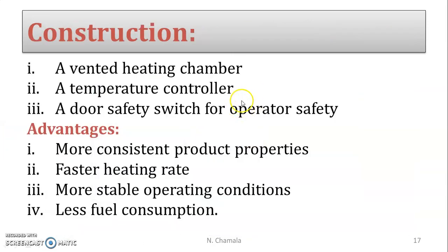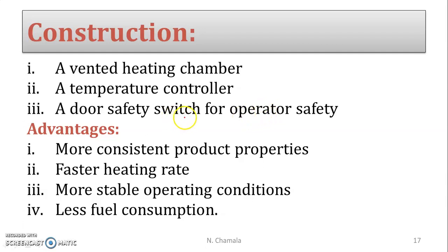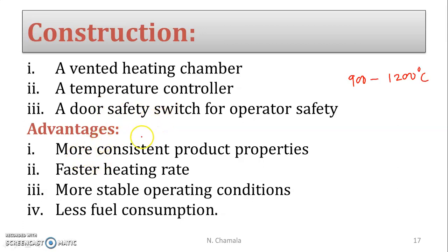Construction of the muffle furnace: it consists of a vented heating chamber at the back side with a small window to pass air, a temperature controller at the top, and a door safety switch for operator safety. The working temperature of the muffle furnace is about 900 to 1200 degrees Celsius, so the door safety switch is there as a precaution.